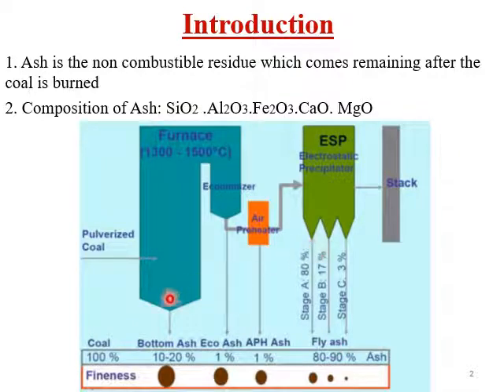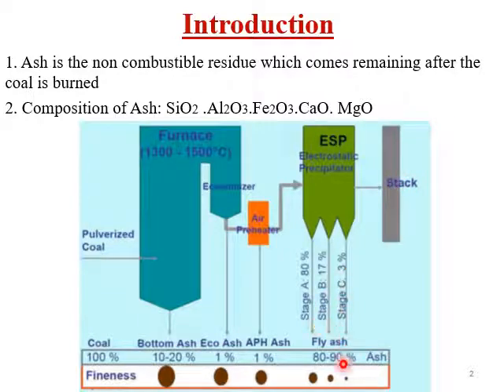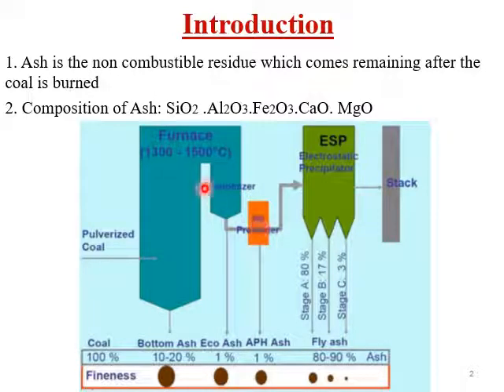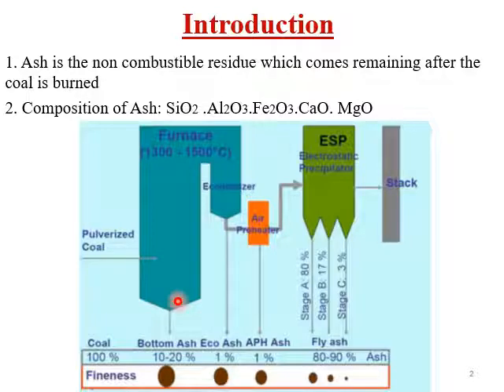The flue gas carries fly ash. When you travel through the electrostatic precipitator (ESP), the majority of ash collected is fly ash — about 80 to 90%. In a power plant, there is 20% bottom ash and 80% fly ash.